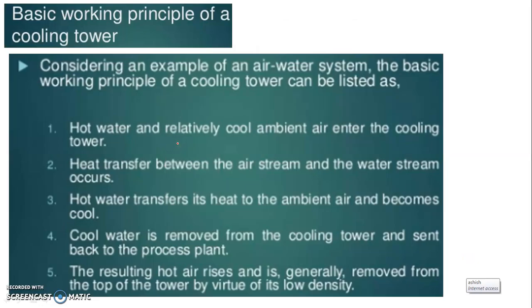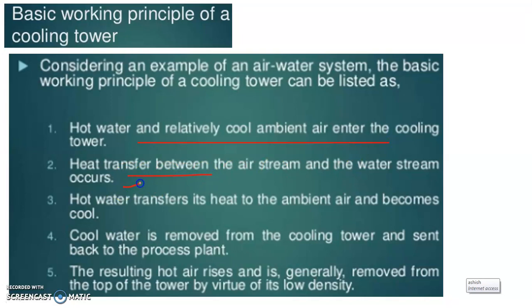The basic principle is as follows: hot water and relatively cool ambient air enter the cooling tower. Heat transfer between the air stream and water stream occurs — the hot water transfers its heat to the ambient air and becomes cool. The cooled water is then removed from the cooling tower and sent back to the process plant. The resulting hot air rises and is removed from the top of the tower by virtue of its low density.